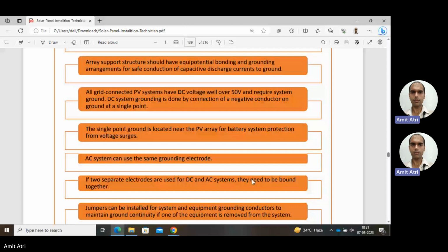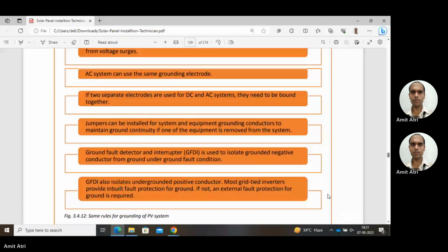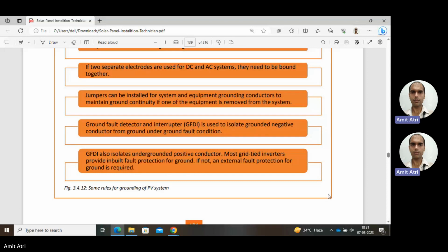The AC system can use the same grounding electrode. If two separate electrodes are used, one for the DC and one for the AC, they need to be bound together. Next rule, jumpers. Jumpers can be installed for system and equipment grounding conductors to maintain ground continuity if one of the pieces of equipment is removed from the system. It should not be that when we remove one component the whole grounding circuit is broken. There should be jumpers that can maintain the connectivity if any component is removed, so the grounding circuit is still complete.